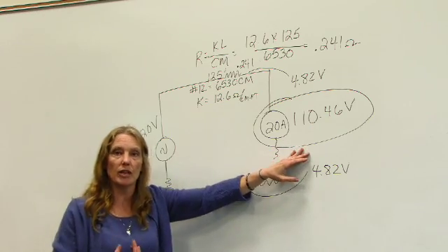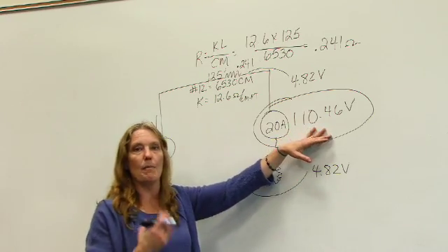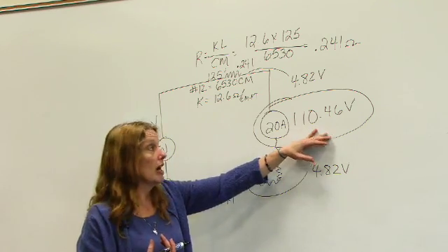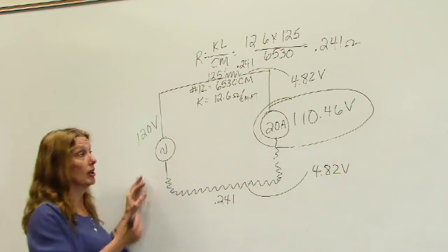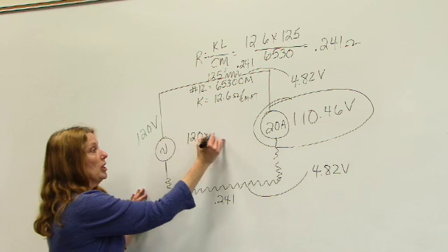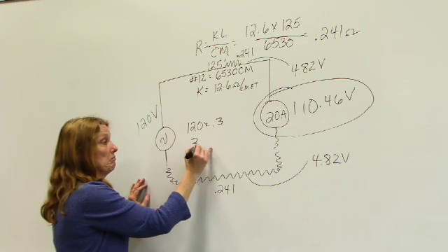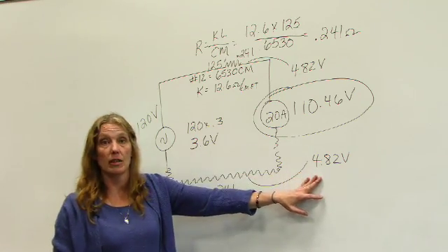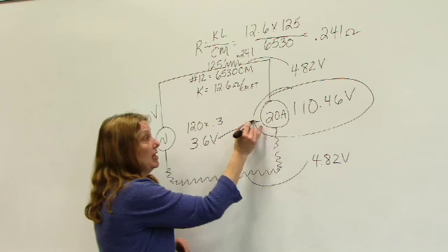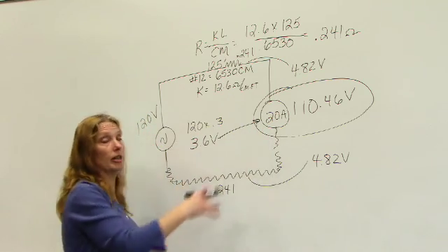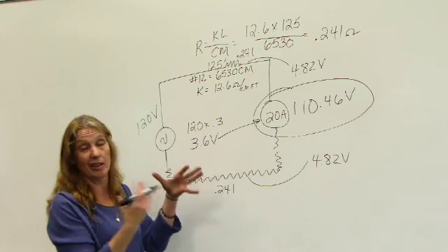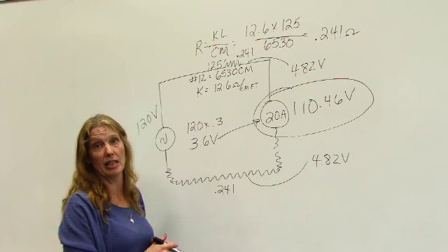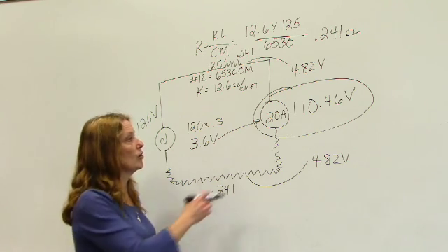The electrical code or the National Electrical Code lets us know that we want a minimum recommended of 3% voltage drop. So I only want to drop, if I've got 120 volts, I take 120 times 0.03, I only want to drop 3.6 volts. I'm dropping quite a bit more here. And that 3.6 volts means overall, the whole circuit. So I would want to calculate something different or I would want to increase my wire size or I couldn't have that receptacle at the end of my yard. I'd have to bring it up closer so I don't drop as much voltage.